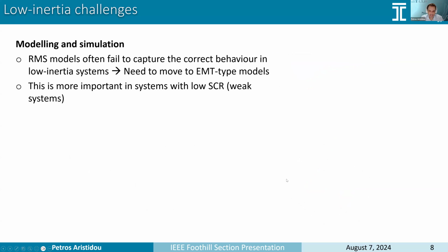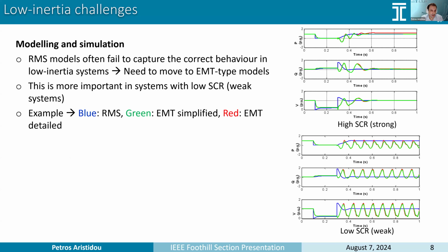Another challenge is looking into the modeling and simulation requirements when we move into a low inertia system, because most system operators use RMS type models in order to capture the dynamics of the system or do time domain studies. But when we have low inertia systems, and especially systems with a low short circuit ratio, this type of models are not accurate anymore, and there is a need to move to EMT type models.